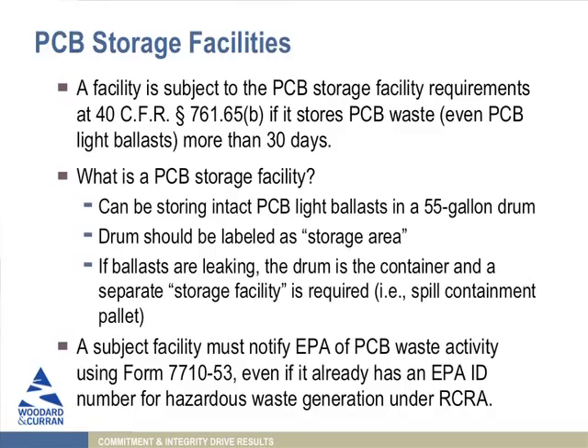So if you have PCB transformers or capacitors, PCB-contaminated transformers or capacitors, light ballasts that are above 50 parts per million - anything at all above 50 parts per million - if you take them out of service and want to dispose of them, you can dispose of them within 30 days and you don't have to worry about the requirements I'm going to talk about now.